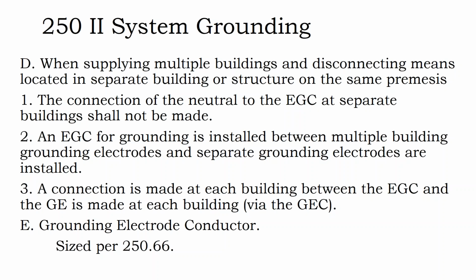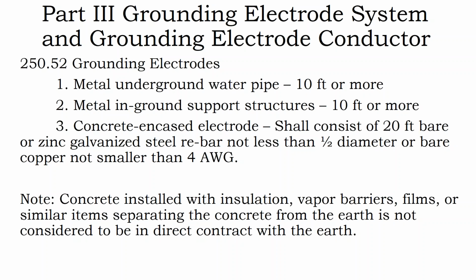main source of supply. You're doing your new construction design, or you may find that the building does not have sufficient path to ground, or, what is more common, you'll find one ground rod on site, and you may need to install a second one. So there are a few instances where you're going to be in charge of speccing out the grounding electrode. On a ground mount system, you may want to put a grounding electrode out on site, not a neutral to ground connection, but a separate grounding electrode.